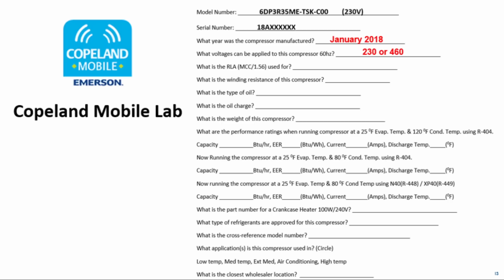Next we get into electricals. The next question I had: what is the RLA MCC over 1.56 used for? So RLA MCC 1.56. What does RLA stand for? Rated load amps. Okay? Rated load amps. If I press on this little eye here, it's used for breaker and wire selection. So if you're a contractor, you own your own business, and you're sizing equipment, or maybe you're running into an issue, you need to check your wire and your breaker size. Okay.